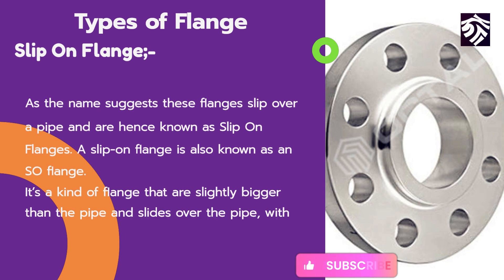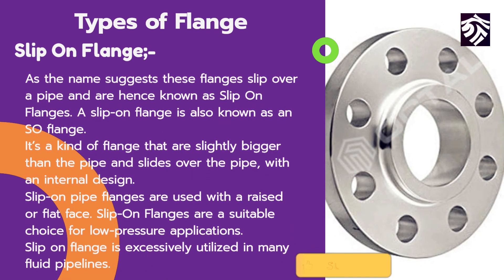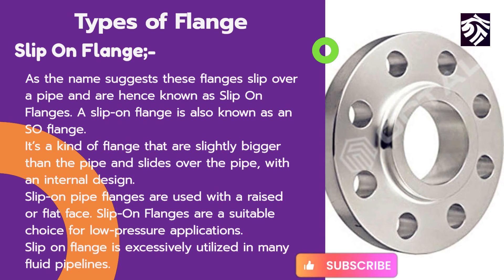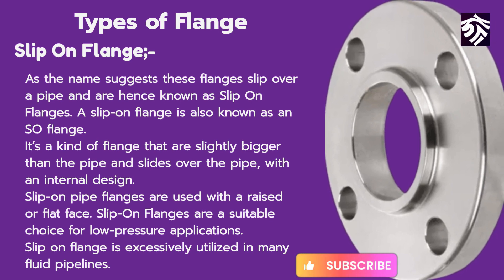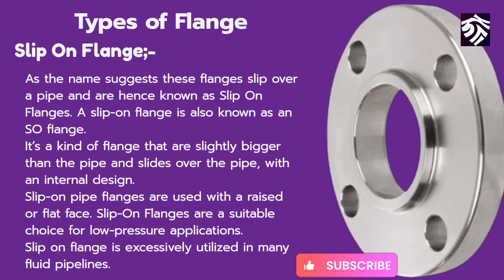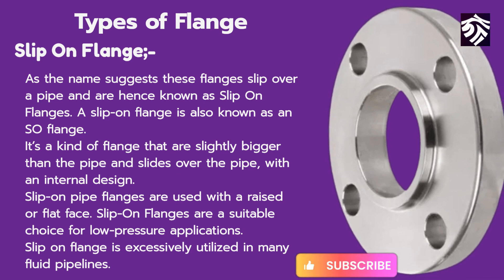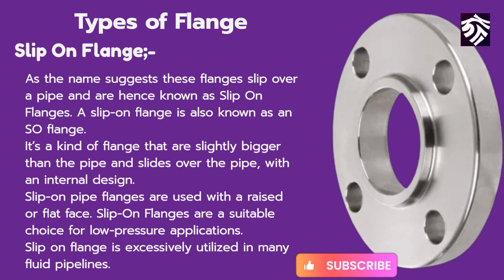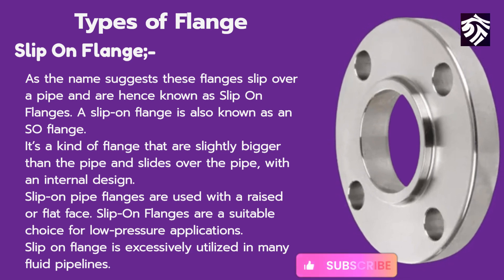The common type of flange is the slip-on flange. As the name suggests, these flanges slip over a pipe and are hence known as slip-on flanges. A slip-on flange is also known as an SO flange. It is a kind of flange that is slightly bigger than the pipe and slides over the pipe with an internal design. Slip-on pipe flanges are used with a raised or flat face and are a suitable choice for low-pressure applications, and are extensively utilized in many fluid pipelines.